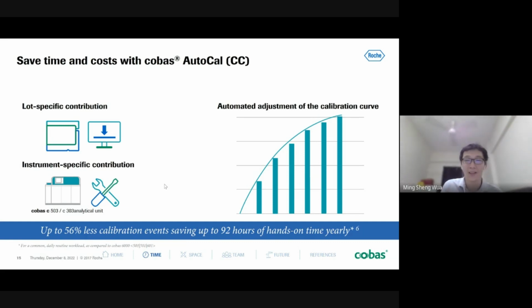As to how it can do this, as I explained earlier, when you do calibration, there are 2 factors. The first factor is from the reagent, the second factor is from the instrument. The factor from the instrument usually stays constant, unless you do PPM or change parts. Otherwise, it remains constant most of the time. So what you download, the variation, is from the reagent. The analyzer is smart, it can combine these 2 factors and automatically adjust the calibration curve for you. This has already been proven. We also have a few studies on this, and they have proven that this AutoCal actually works. I'm not sure whether I answered that question or not.